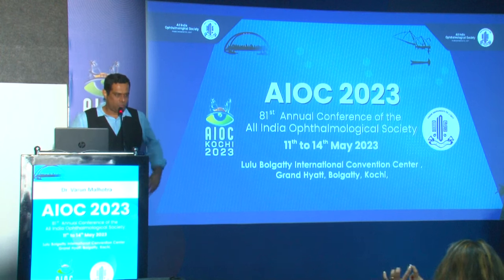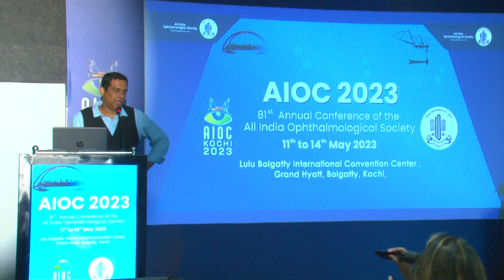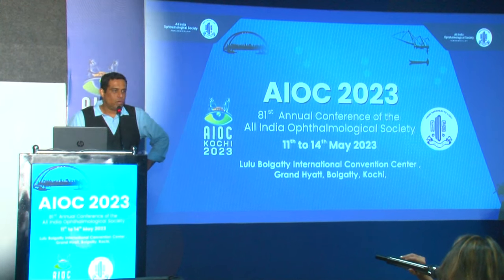For a posterior polar cataract, leave approximately 200 microns posteriorly in the femto settings. For posterior polar cataracts, I make six pieces but do not go for further segmentation. Lens softening is more important specifically for harder cataracts — for cortical, PSC, or NS grade 1, I don't use softening; it is only done for grade 3 and above. Regarding gas bubbles, earlier machines produced more bubbles; nowadays we hardly get them, which is much better.